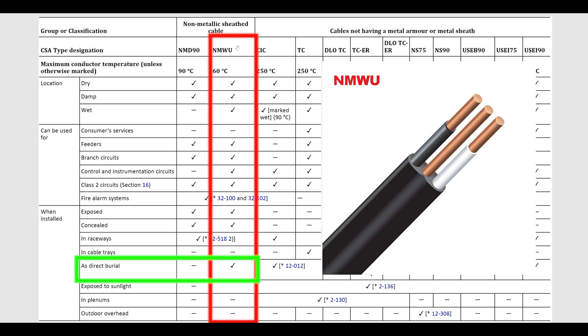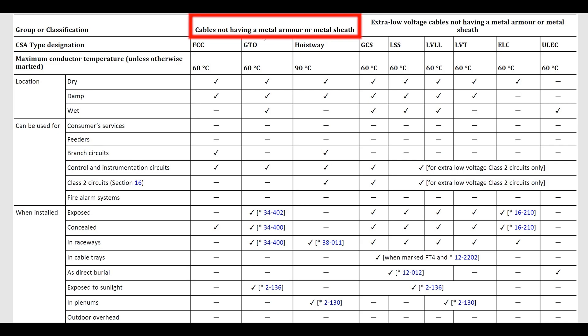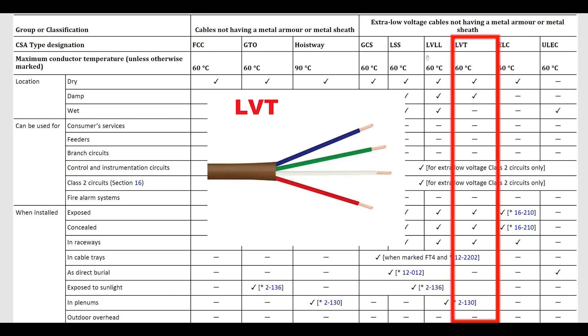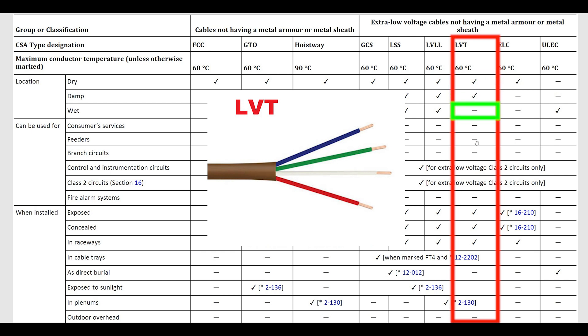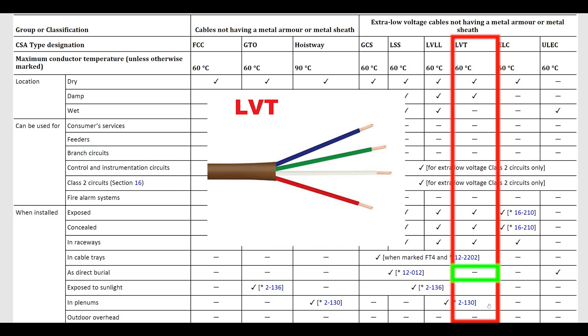Bunch of other types here—not so common cables not having a metal armor or metal sheath. Extra low voltage cables are maybe even more common. Let's talk about LVT. LVT cables usually used for maybe a thermostat or maybe your doorbell: dry, damp, not good for wet, not good for a couple different uses either. Exposed, concealed, and raceways are all okay. Cable trays is okay and plenums is okay, even exposed to sunlight under certain conditions. LVT, very common.